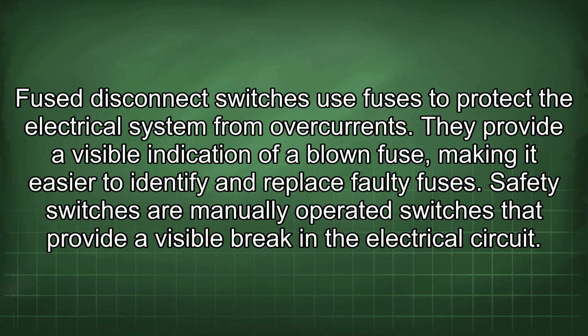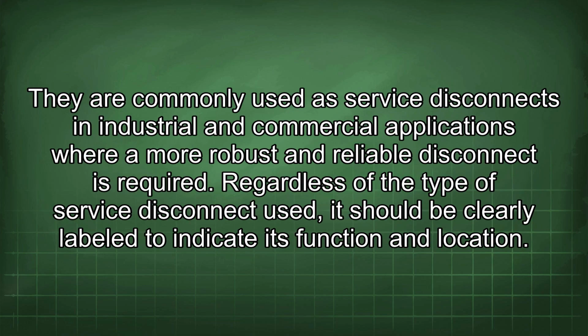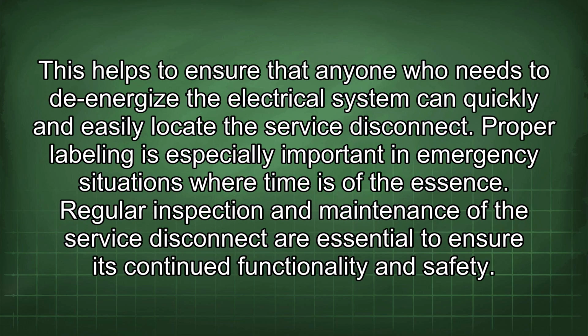Safety switches are manually operated switches that provide a visible break in the electrical circuit. They are commonly used as service disconnects in industrial and commercial applications where a more robust and reliable disconnect is required. Regardless of the type of service disconnect used, it should be clearly labeled to indicate its function and location. This helps to ensure that anyone who needs to de-energize the electrical system can quickly and easily locate the service disconnect. Proper labeling is especially important in emergency situations where time is of the essence.